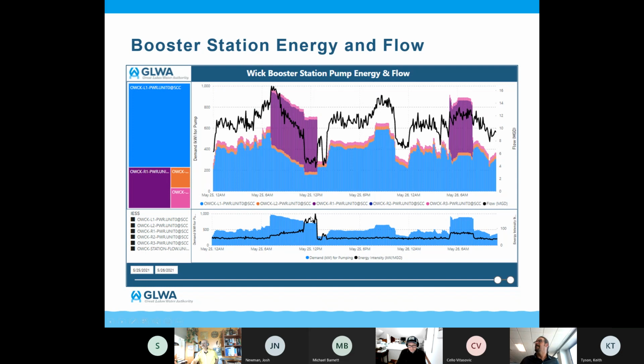So you can see when we're performing poorly. Here our flow rate is down here, but our energy usage is up here. That's indicated on this one, that our energy intensity is really high. So these can feed into how to avoid those situations being on peak. There are sometimes processes that are unavoidable, where we have to be inefficient, but when we're inefficient, we make sure we're at least not on peak and it's not costing us more.